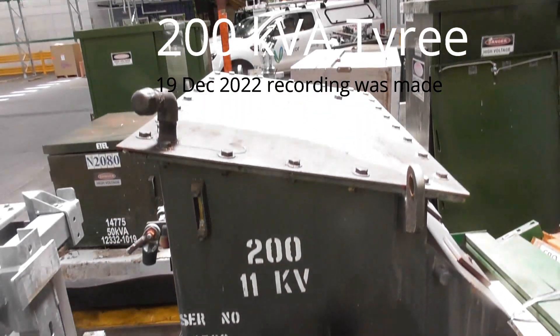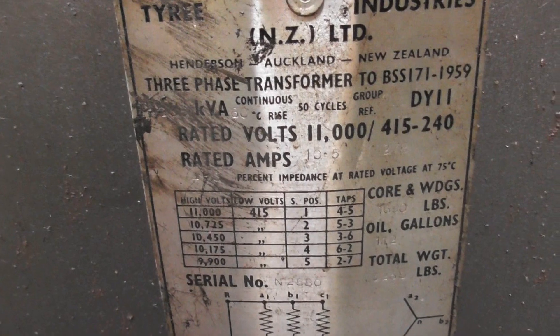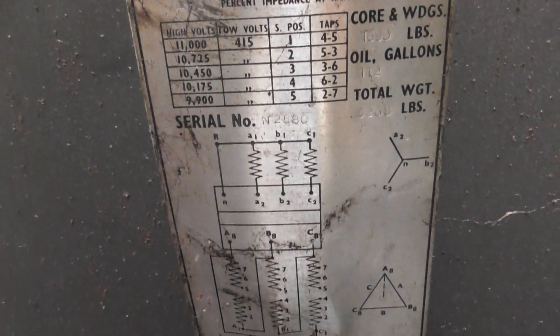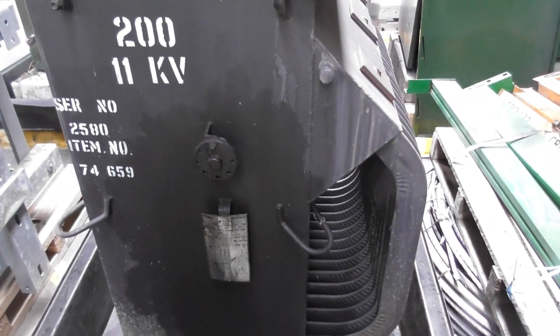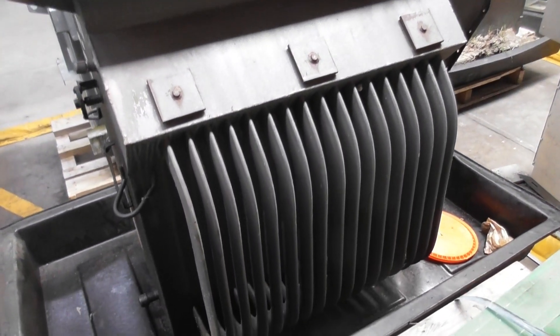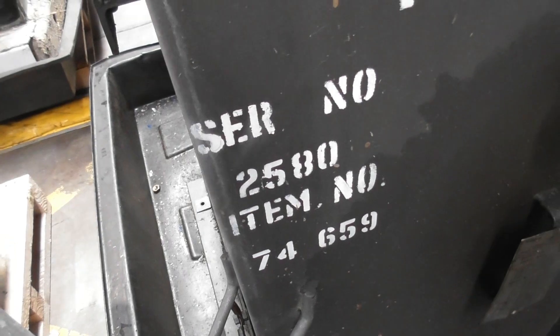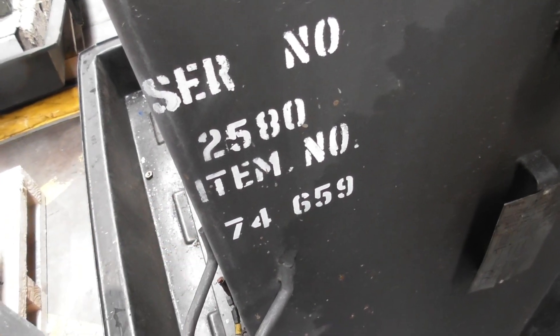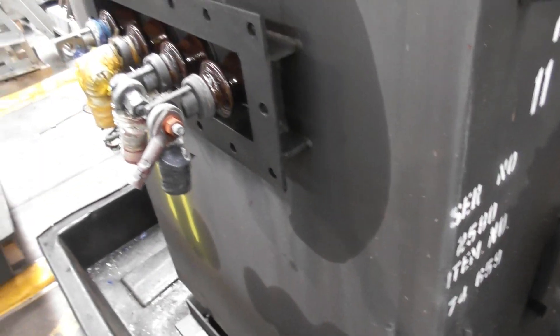Number two — this is a Tyree transformer that came out of a shell as well. The nameplate is pretty hard to read, about 200 kVA. It's a pretty standard design with option for bushings on the outside, but there's a link box on the right-hand side. I'll show you shortly. Serial number two five eight zero, item number 74 — that would be 1974 install, going on nearly 50 years. Blue, yellow, red, neutral.